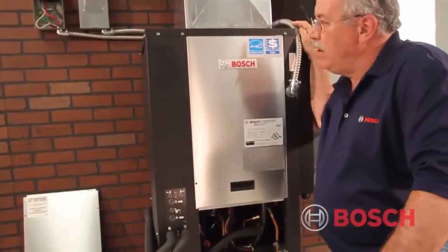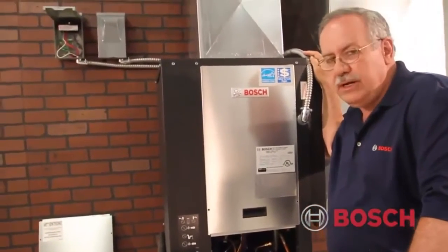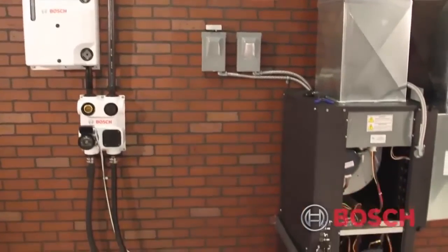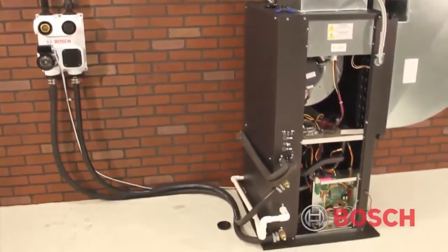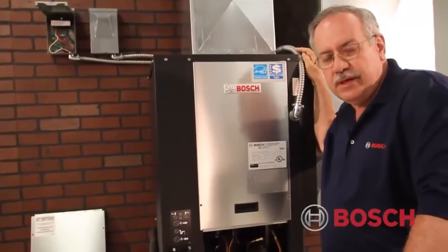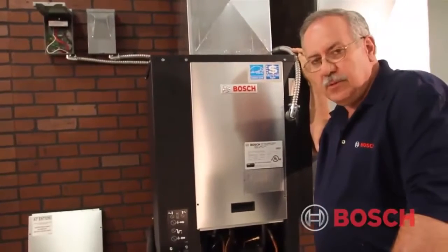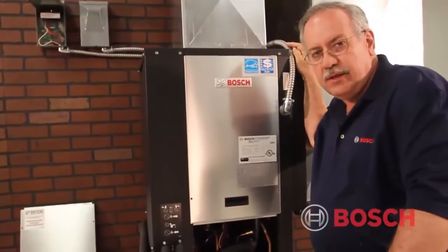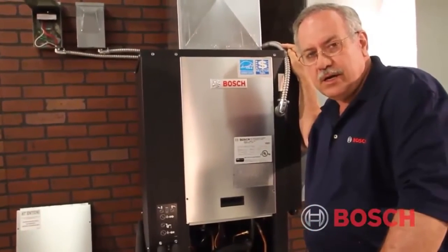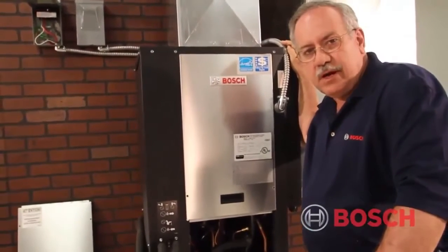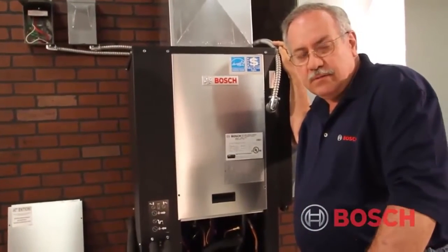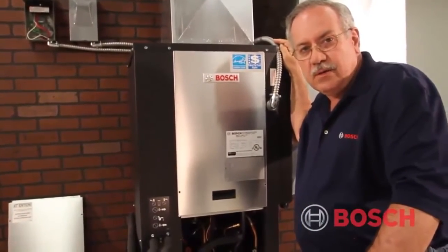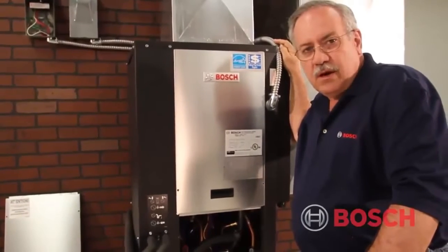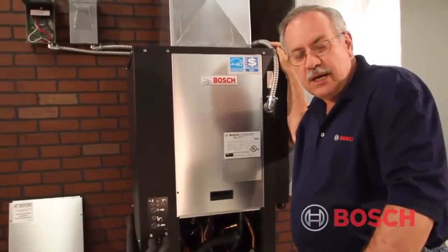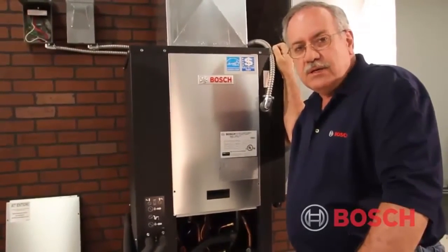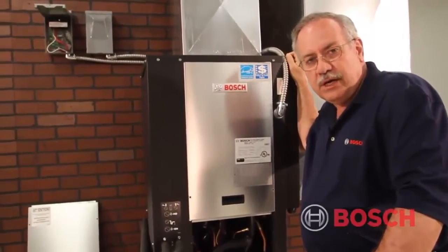Okay, so now we're going to discuss actual waterside diagnostics. With a Bosch geothermal heat pump, such as we have here, this TA025, water is everything. Without the proper gallons per minute flowing through the coaxial heat exchanger and therefore into the ground heat exchanger, we will have no effective heat transfer. We will have no value. So what we've got to do, we've made sure that hopefully we have the right electricity and we also have the right airflow. So the next thing is to check the waterside diagnostics.